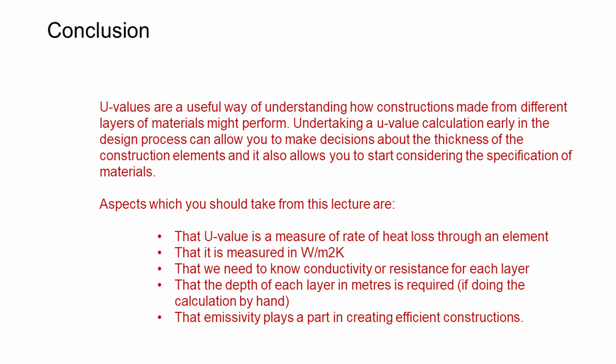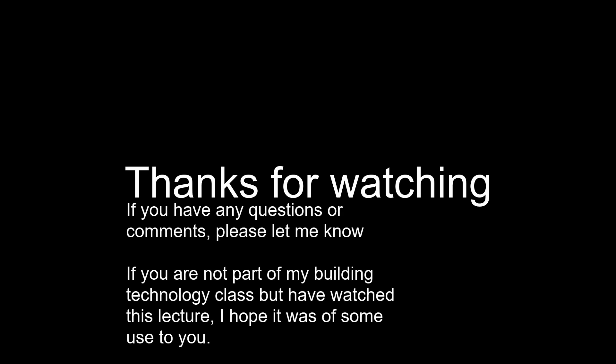In conclusion, U-values are a useful way of understanding how constructions made from different layers of materials might perform. Undertaking a U-value calculation early in the design process allows you to make decisions about the thickness of construction elements and the specification of materials. Key points from this lecture: U-value is a measure of the rate of heat loss through an element, measured in watts per metre squared kelvin. You need conductivity or resistance for each layer, and the depth of each layer in metres. If doing the calculation on a computer, they tend to work in millimetres. Emissivity plays a part in creating efficient constructions. The next lecture will be a worked example using real values, followed by one done through a calculator.